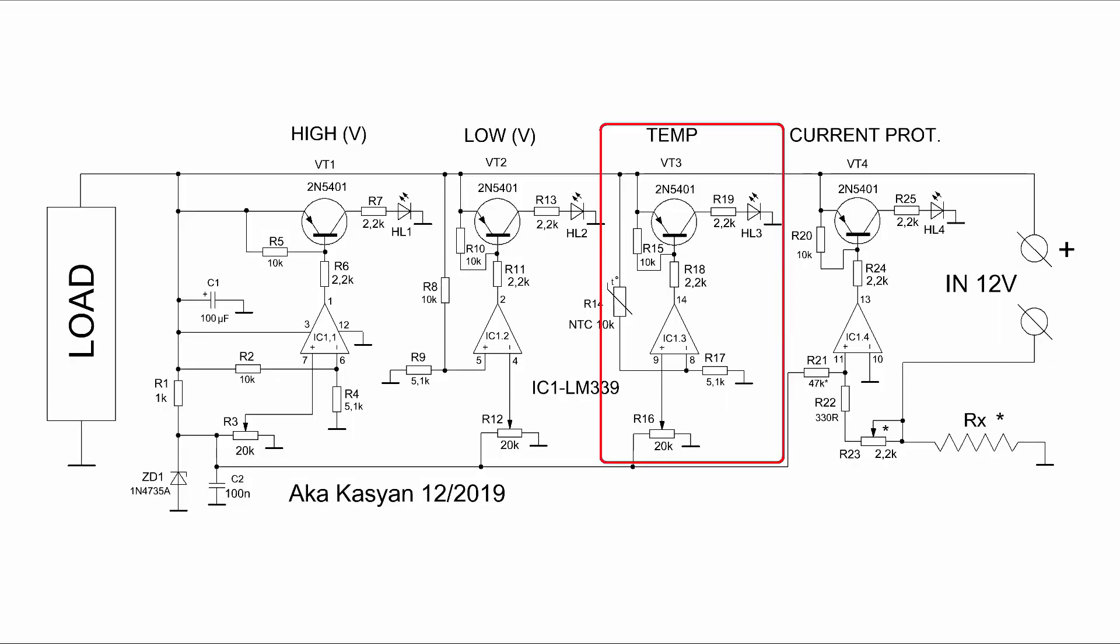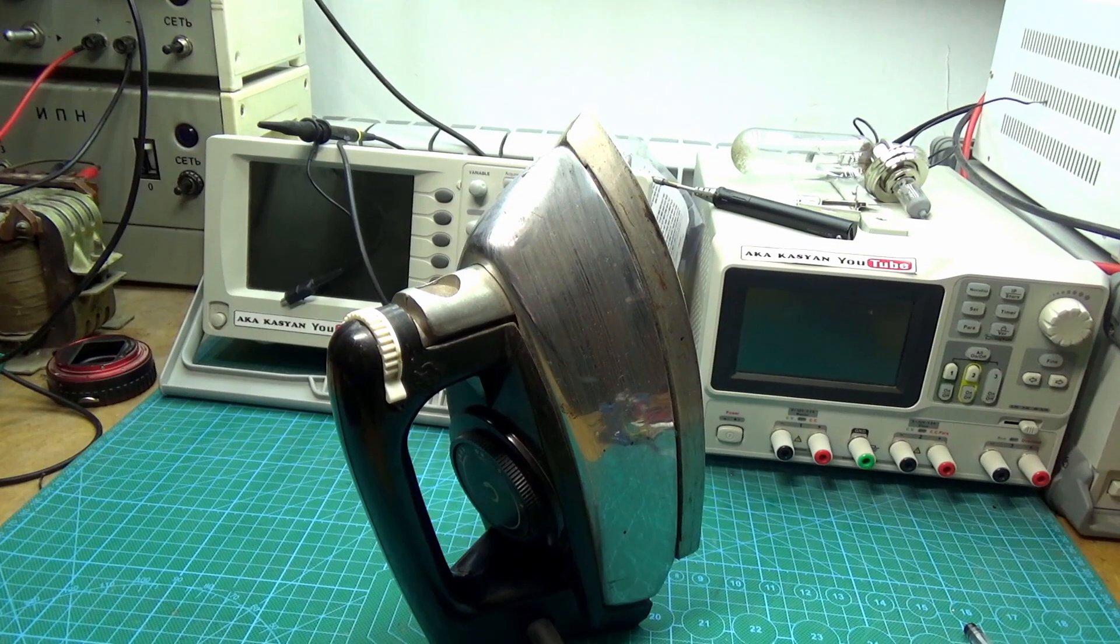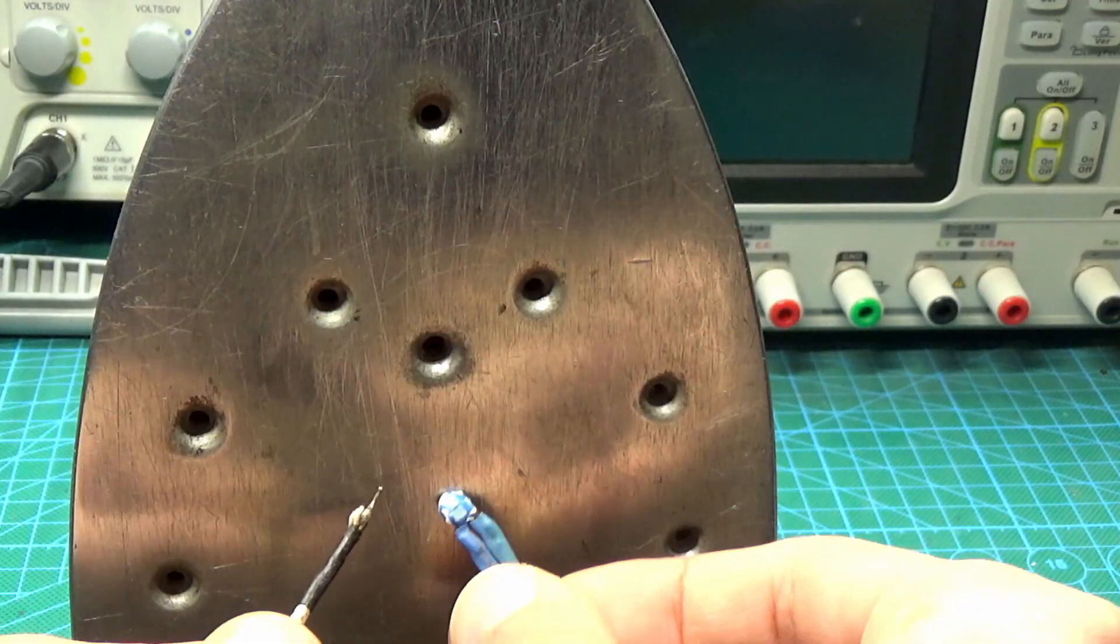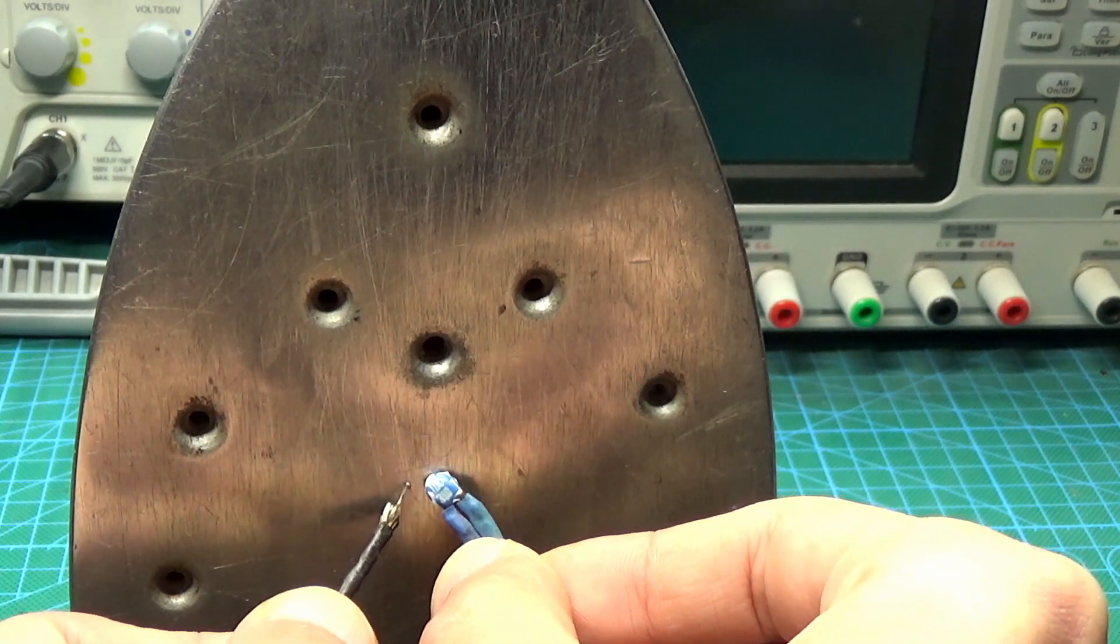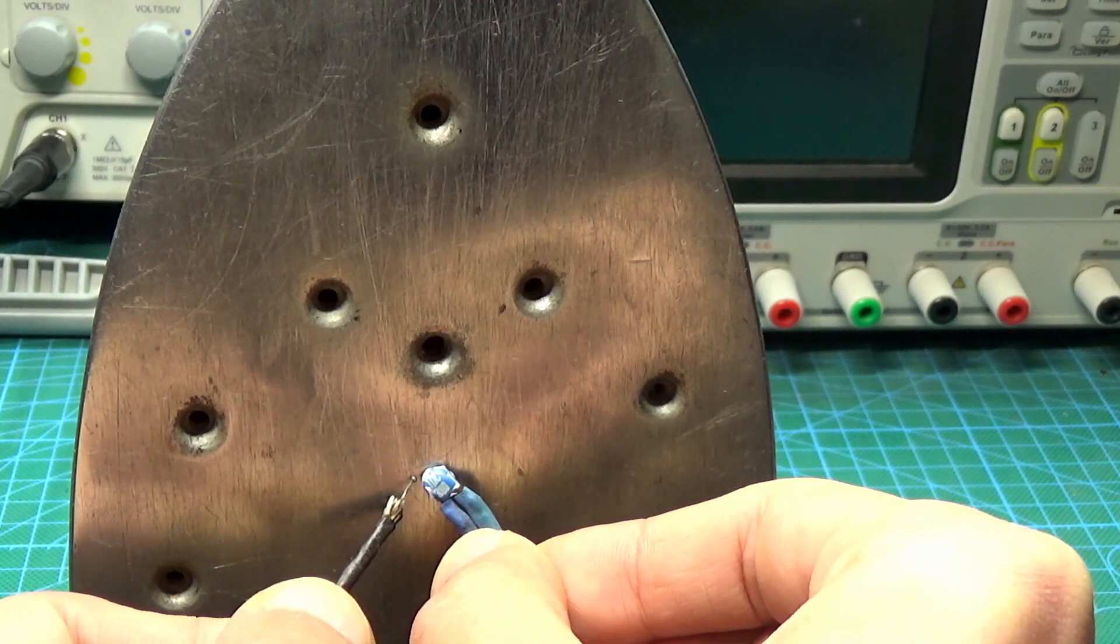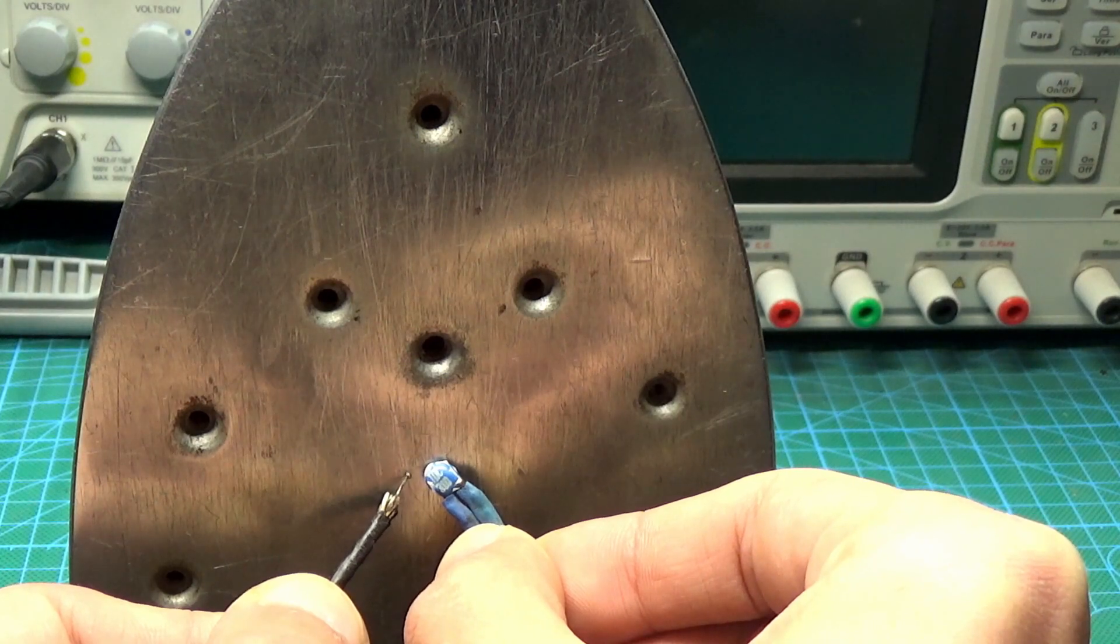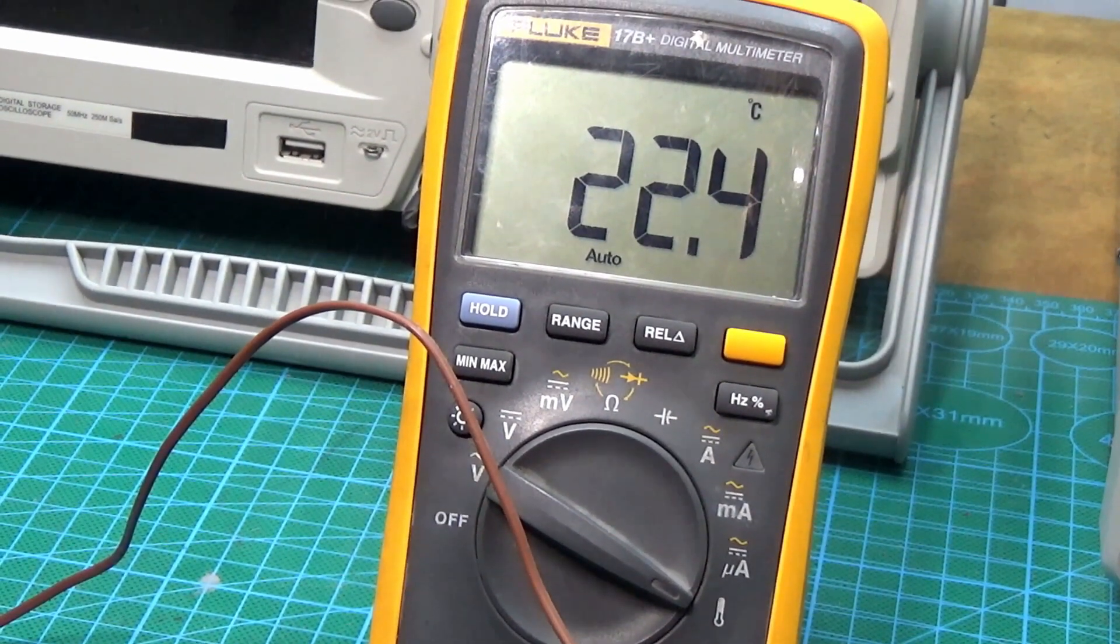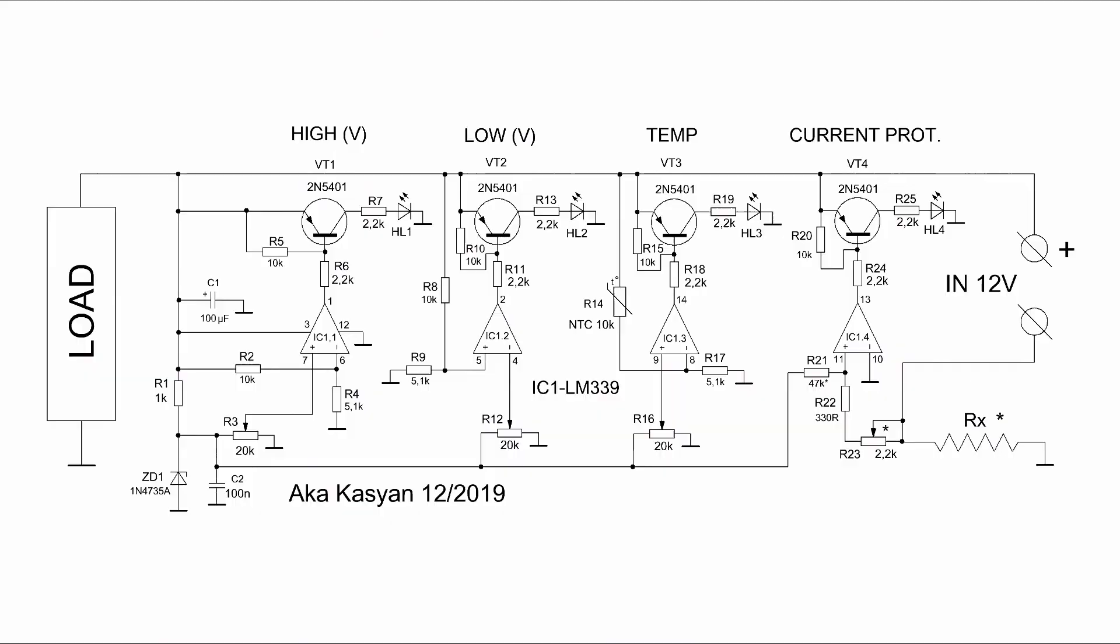To do this, you need any heat source with the ability to adjust the temperature, for example an iron. The thermocouple of the reference thermometer and the thermistor of the device are placed on a heated surface. Warm up to the temperature at which the protection should work. The temperature is monitored by a thermometer. Then we are rotating the tuning resistor until the LED lights up.